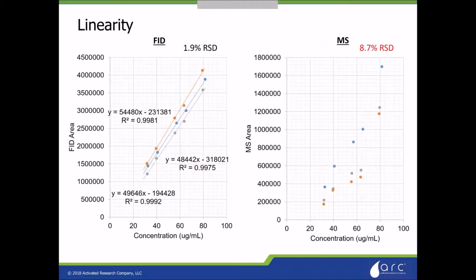The other reason it's important with the FID, and what we see a lot of our customers doing, is pairing the FID with the mass spec using a post-column splitter. Agilent has a very good purged post-column splitter technology where you can take the end of your column and split it into up to three different flow paths and control the pressure of that splitter with an EPC so that you can have a split ratio regardless of your temperature ramp. And that gives very accurate results, allows you to split, for a lot of our customers, from an FID polyarc as well as a mass spec. And so in a single injection, you can get quantification and identification.